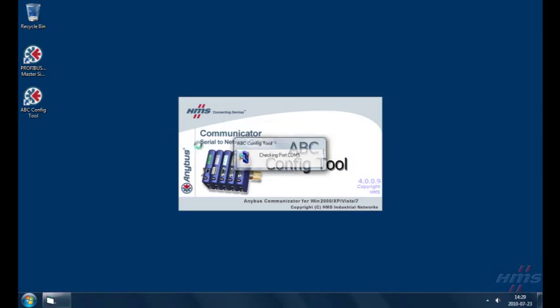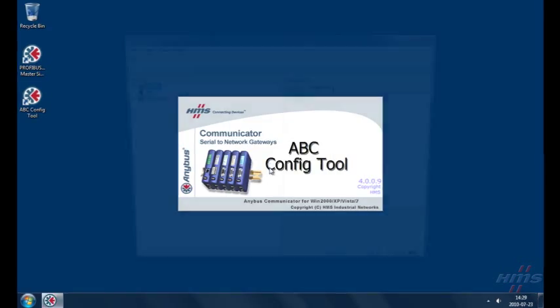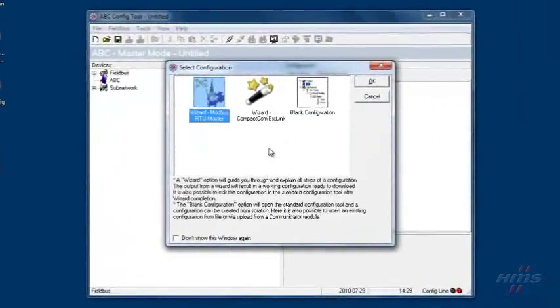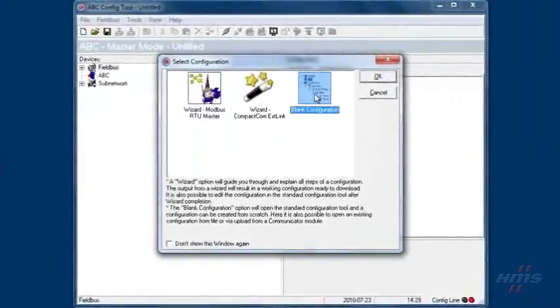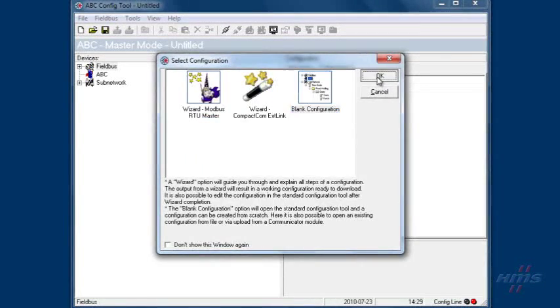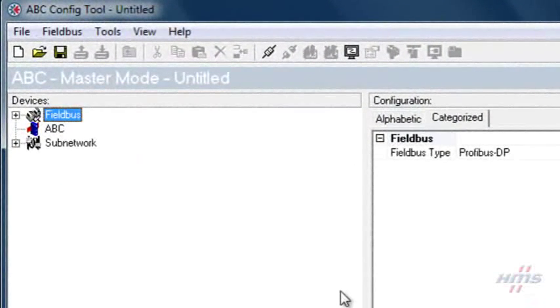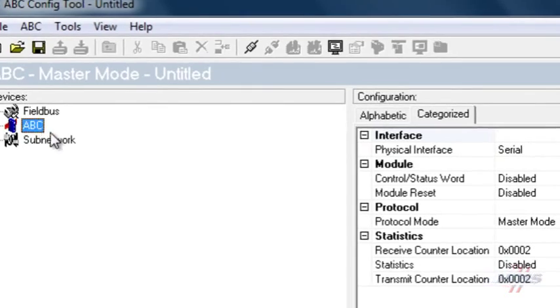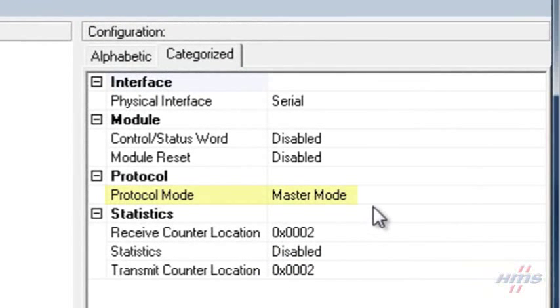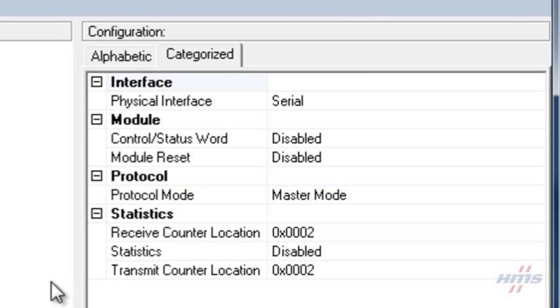We begin by starting the ABC config tool and select an empty configuration. Our communicator fieldbus type is Profibus DP. We select the ABC entry to verify that the protocol mode property is set to master mode, which makes the communicator operate as master on the subnet.